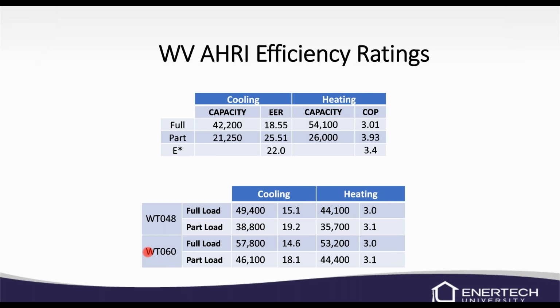These are some of the efficiencies. You can see on the bottom here, we've got the WT, which is a single stage. We've got it in the 048 and the 060. And we're just comparing the two-stage unit with the variable speed on the top here. When we're running in our part capacities, we're going to be running about a 3.9 COP at times. So the lowest we're probably really going to see in heating is about a 3. So we're definitely more efficient than our two-stage water-to-water unit, and we've got good capacities as well.